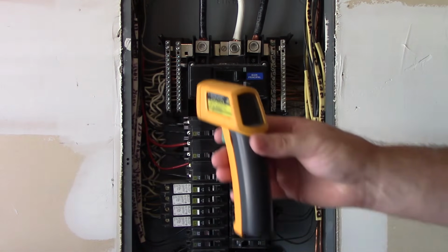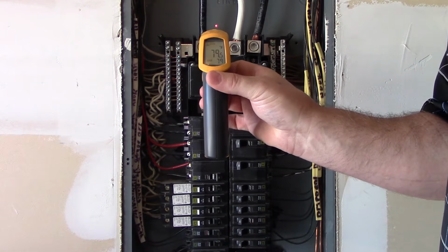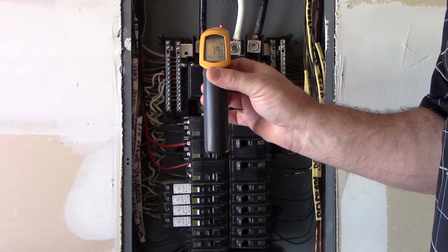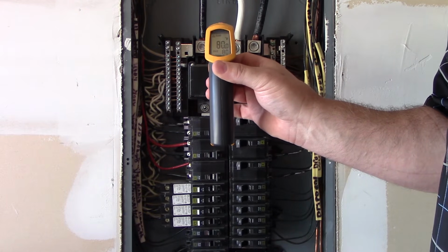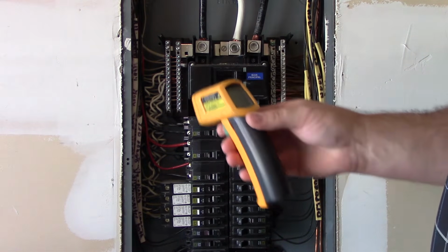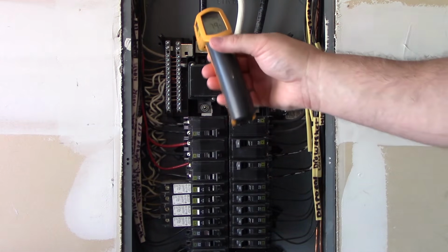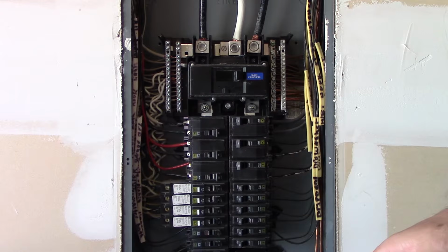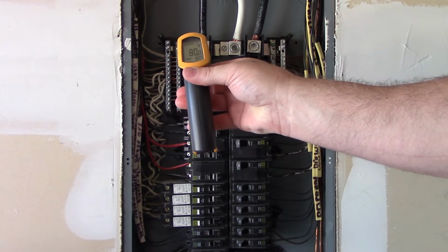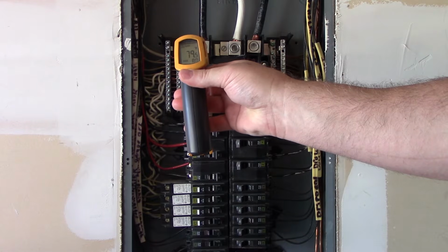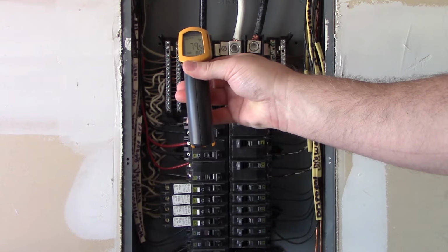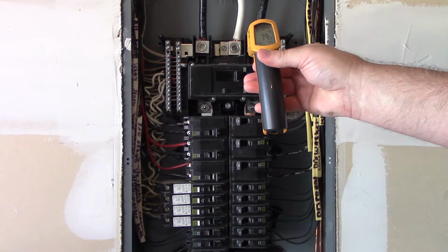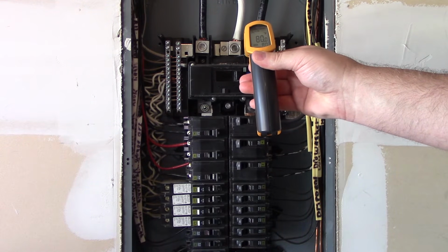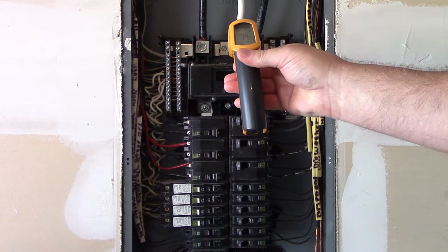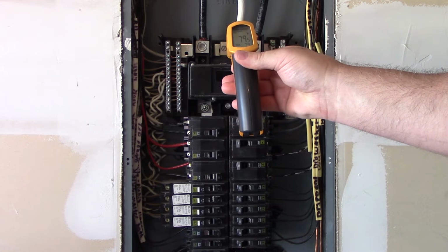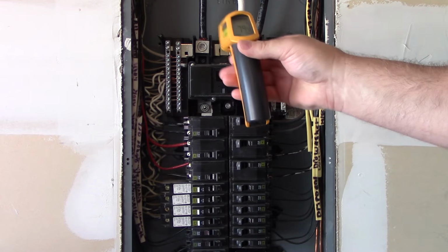The first baseline that I like to do is to go to the actual cabinet itself. This cabinet is 79 degrees, and it's mounted against a brick wall on the other side here, so it's about 79 degrees. The next thing I'm going to do is shoot the actual lugs that my ungrounded conductors go to. I'm going to shoot inside the actual lug here, and this is about 79, 80, about the same as the cabinet. Then I'm going to go over here and shoot the other, and this is about 80, about the same as the cabinet. Then I'm going to shoot my grounded conductor, and it's about 79. Okay? So that's my baseline.